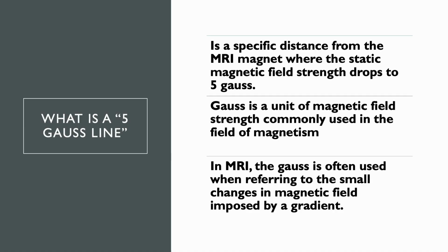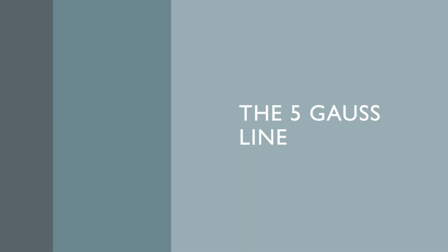Let's begin by defining a 5 gauss line. A 5 gauss line refers to a specific distance from the MRI magnet where the static magnetic field strength drops to 5 gauss. Gauss, on the other hand, is a unit of magnetic field strength commonly used in the field of magnetism. In MRI, the gauss is often used when referring to the small changes in magnetic field imposed by a gradient. Please note, the distance of the 5 gauss line is not fixed. It depends on the strength of the MRI system.